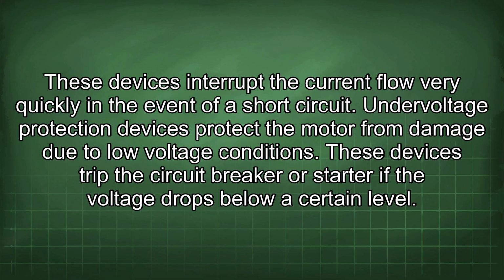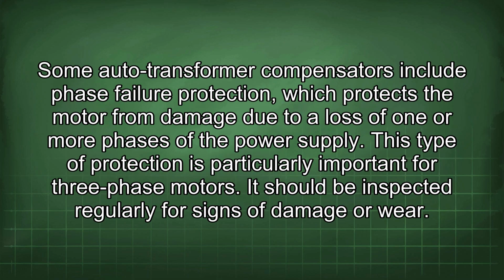Undervoltage protection devices protect the motor from damage due to low voltage conditions. These devices trip the circuit breaker or starter if the voltage drops below a certain level. Some auto transformer compensators include phase failure protection, which protects the motor from damage due to a loss of one or more phases of the power supply. This type of protection is particularly important for three-phase motors.